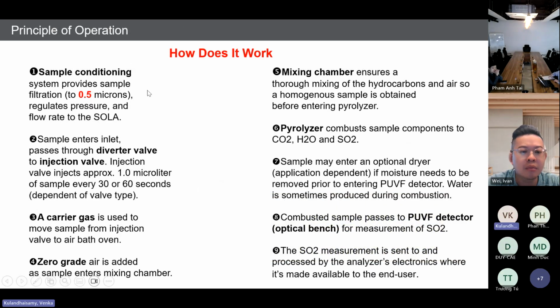So how does our SOLA IQ work? How does it operate? The first thing, the sample conditioning system has to provide the process sample to our SOLA analyzer. That process sample must be filtered down to 0.5 microns. The filtered sample is injected into our SOLA IQ analyzer via an injection valve. That injection valve is either a linear type or a rotary type. So we have two types of injection valve. Based on the application, the customer can choose either rotary or linear type.